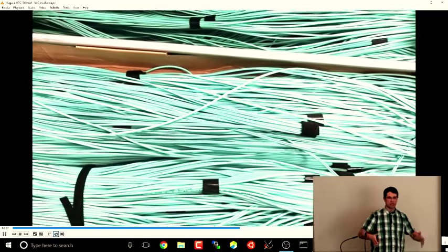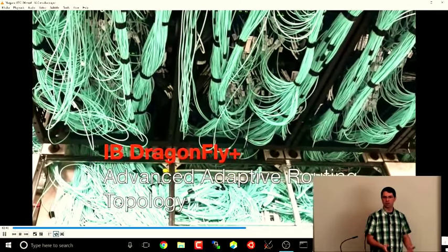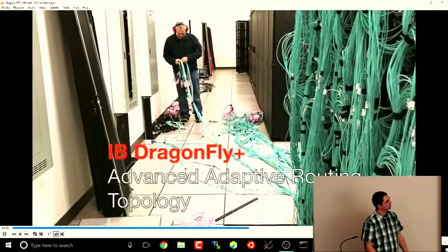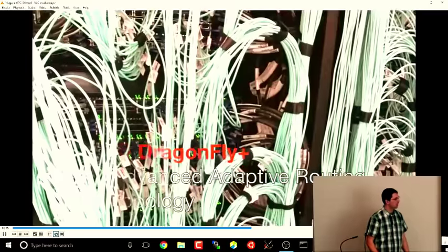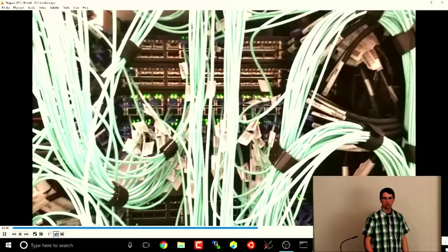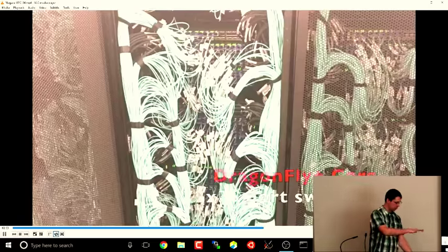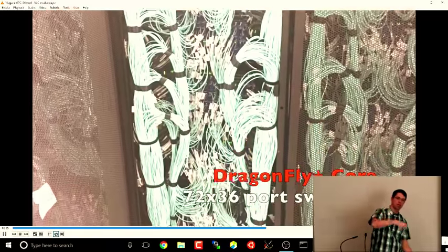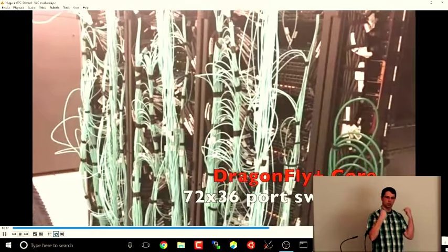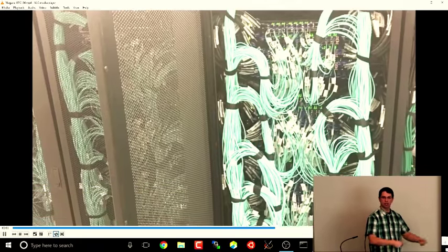The racks actually come fully assembled from the factory, but the cabling is the stuff you can't do in advance. So that's actually the biggest part. There's about 100 man hours of just cabling. Plumbing's all under the floor. There's an 18-inch raised floor, so about 1.5 feet, and all the plumbing's under there. You just pull up the tiles and adjust it. That's why it's fairly flexible.